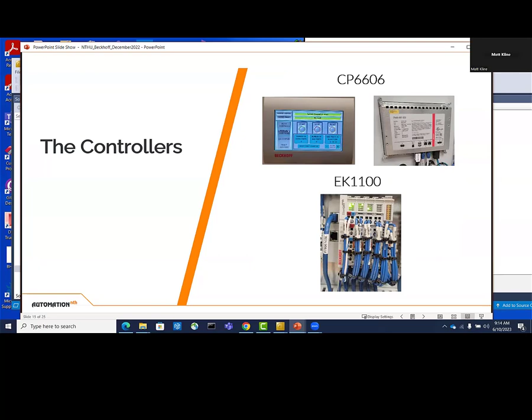The CP6606, which is the HMI, has a little remote bus module, EK1100, built into it. I'm going to show you a little difference between these EK1100s. With the supply shortage, this was the only one available, and the difference is it has an M8 Ethernet connector on it instead of a standard Ethernet cable like this. So you had to buy special cables for it. It's kind of a pain, but that's the only thing that was available at the time, whereas these use regular Ethernet cables, and they would be more cost effective if you were to get a hold of these. And at one time, I think 10,000 of them were on back order.